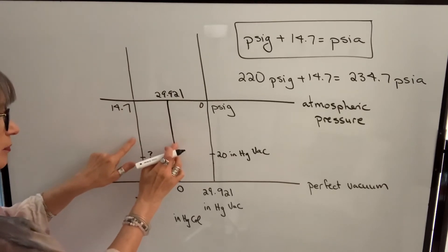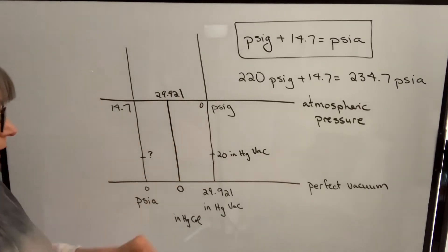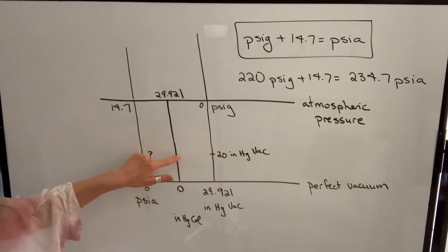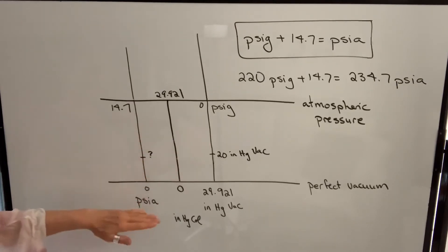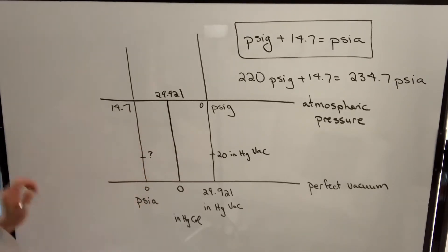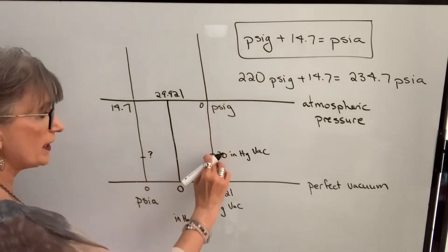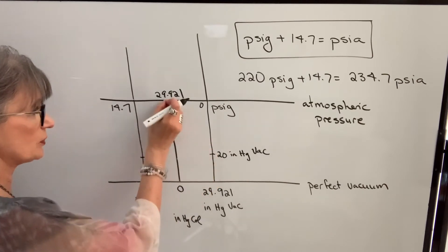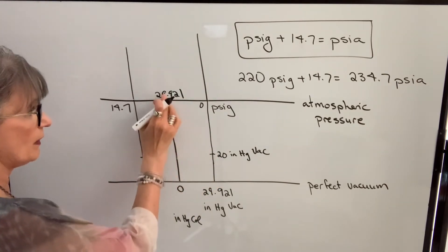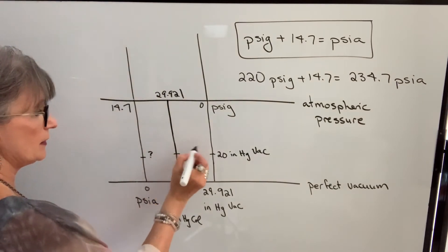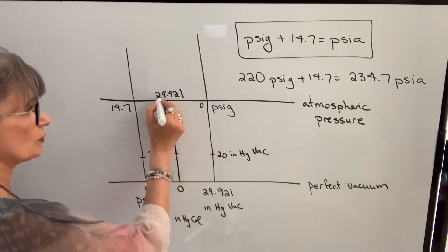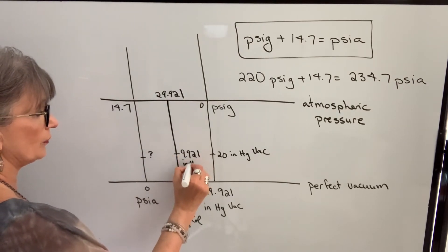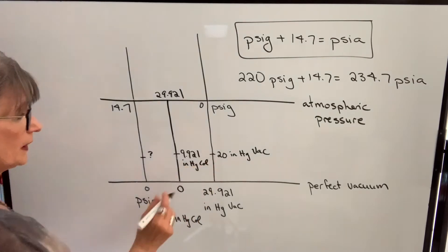Because inches mercury column starts at zero at the same place as PSIA and increases with higher pressure, we can set up a direct proportion between those two measurements. I need to first convert 20 inches mercury vacuum to inches mercury column. If I'm down 20 from the top, I subtract 20 from 29.921 and get 9.921 inches mercury column. These two values are equivalent.